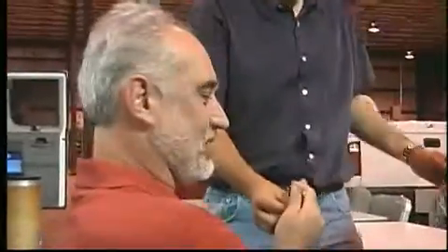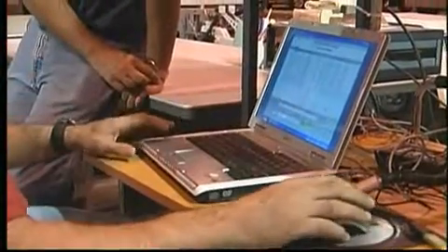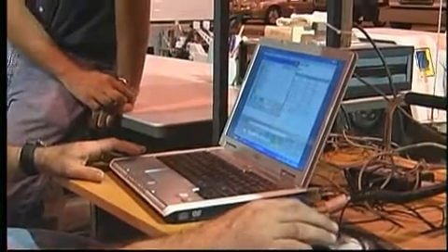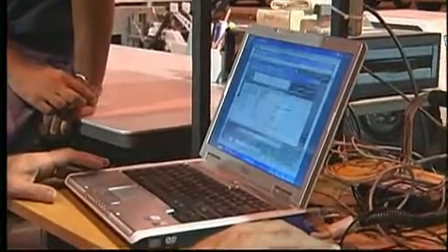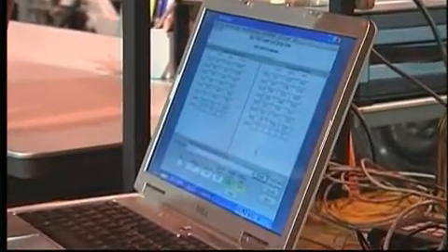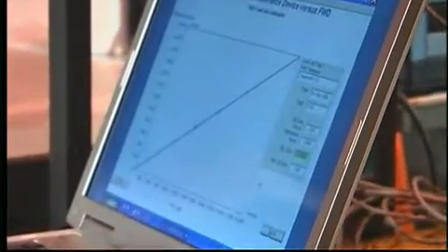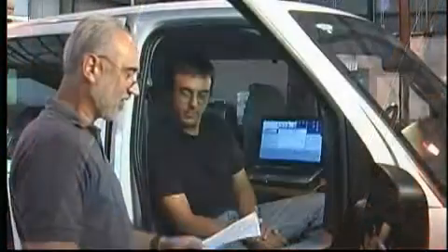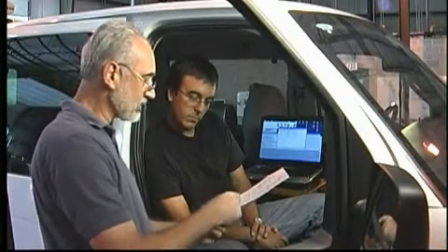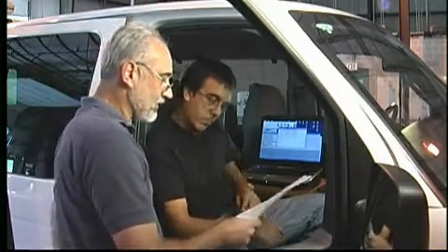Here you go. Thanks, Dan. Load cell 5. Okay. Thank you. There it is. Those numbers look pretty good. Nice. Let's take a look at the graph. Oh, look at that graph. It's beautiful. Here's a copy of your calibration, Dan. It has the final gain factors on it. We'll need to input them in your computer. And sensor 3, you might want to keep an eye on it during the course of the year. Okay. You want to read them off to me? Sure.